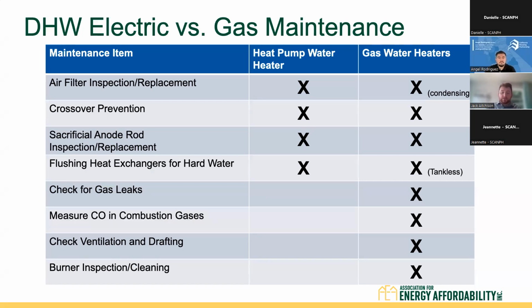One of the reasons why crossover prevention is so important for heat pump water heaters, someone asked the question, with reduced recovery, how do you make sure people have hot water? Well, if you have an inflated load on your recirculation system, it's going to be even harder to maintain that load with a heat pump water heater because the recovery is so low. So it's very critical, in order to maintain adequate hot water with a heat pump water heating system, to take crossover prevention into account in your maintenance plan.